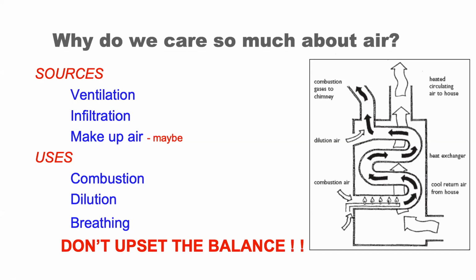So if you look back at, and of course they're being used for combustion dilution and then just the distribution air or breathing. If you look back at this and say, well, I want to get control over my building structure, how leaky it is, it's drafty, let's really address the infiltration. So when you do address the infiltration, that might actually be a source of air for combustion or for dilution.